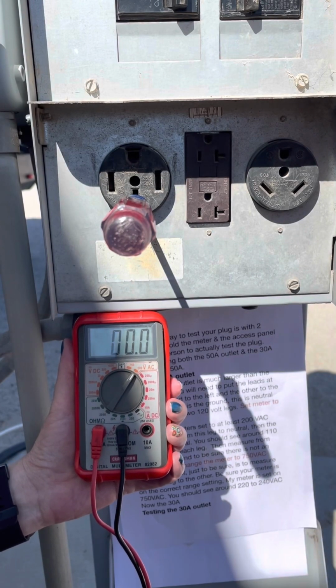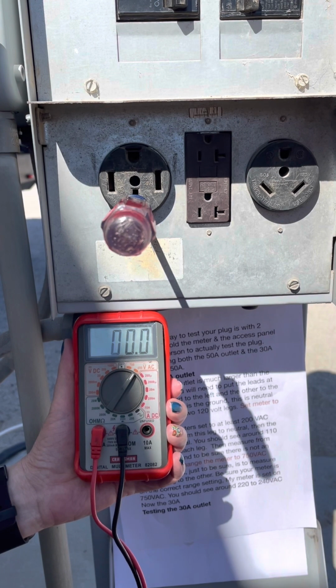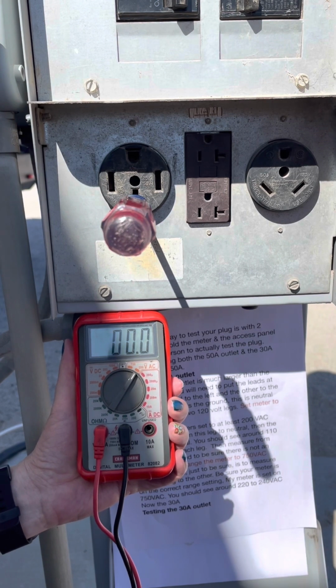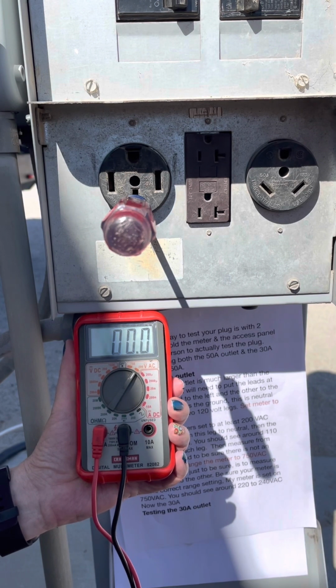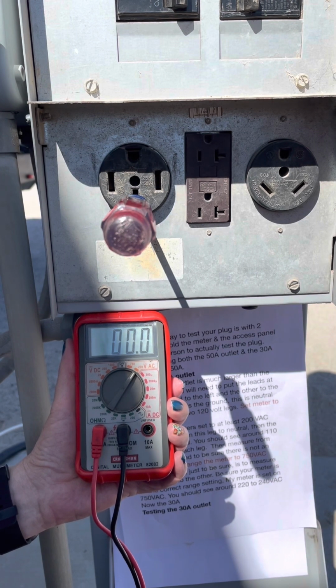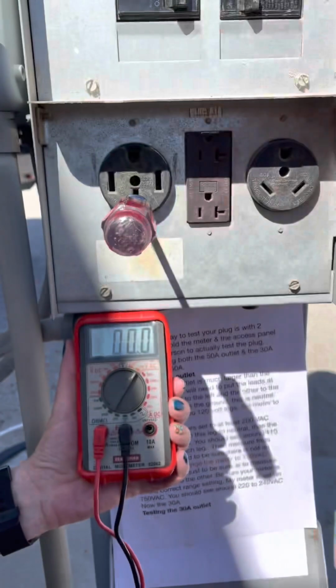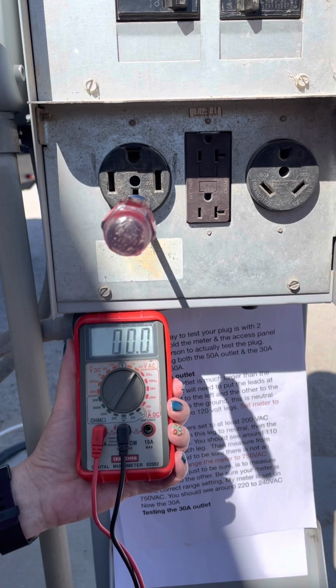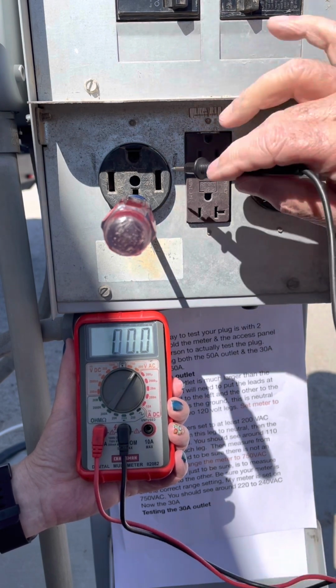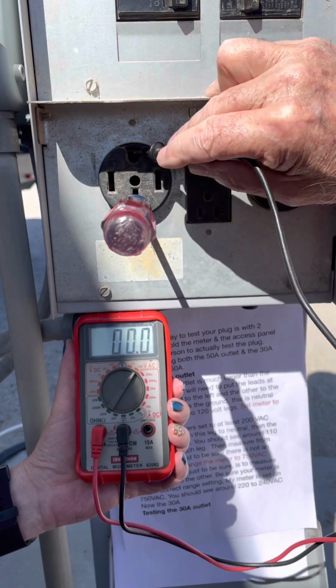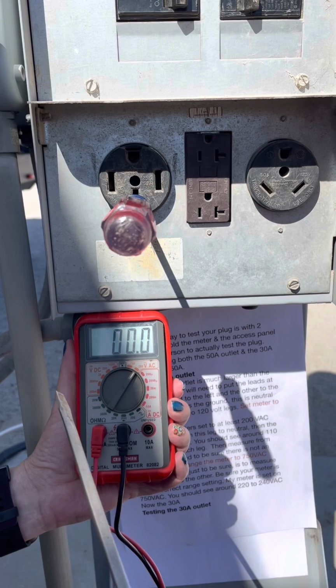The easiest way to test your plug is with two people: one to hold the meter and the access panel, and the other person to actually test the plug. I will show testing both the 50 amp outlet and the 30 amp outlet. First, the 50 amp outlet. The inside of this outlet is much larger than my meter leads, and in fact the contact is deeper than my probe will reach. So I'm carefully going to use a flat blade screwdriver to give me access to the contacts. This is a hot leg, this is a hot leg, this is ground, and this is neutral. First thing we want to do is measure from each leg to neutral.